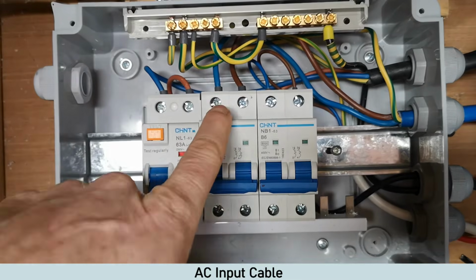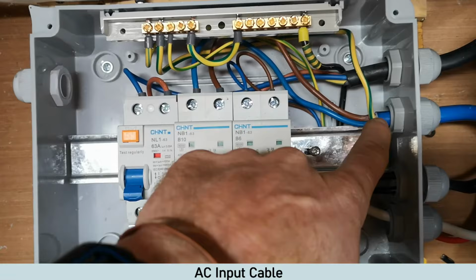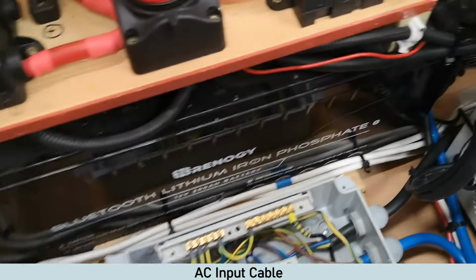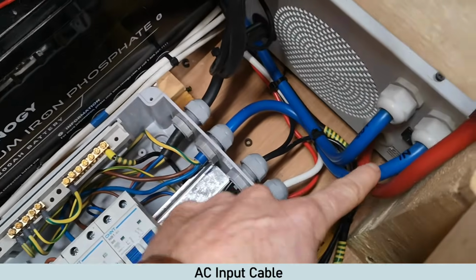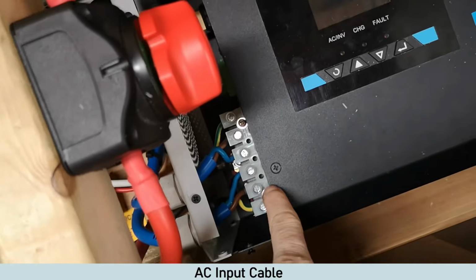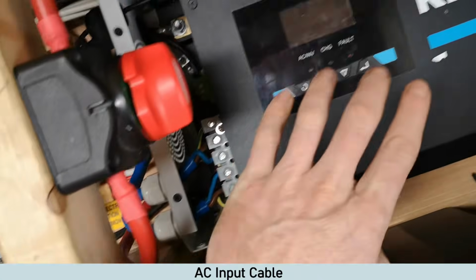So from this breaker then you can see the cable there which goes out, which is this blue one. So the blue cable for us then routes round, and it's the input. I've just removed the cover for this now. That's the input side of the inverter charger, so that's the power coming in.